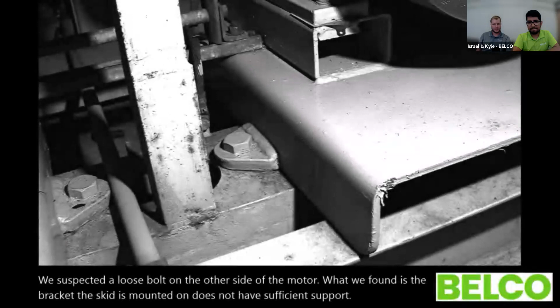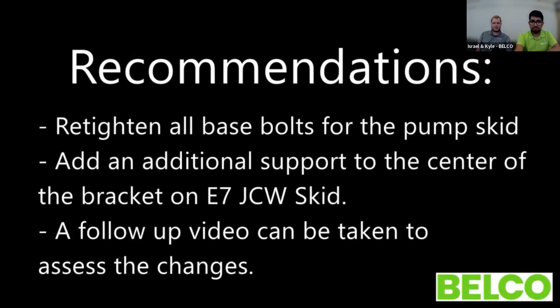And then this is the back of the base plate. You can see that the structure it's mounted on isn't very rigid. It's very flexible, giving it a lot of room to move. Our recommendations were to retighten all the base bolts and add additional support there to make it more rigid. After that, we got them to install lateral supports on the skid.